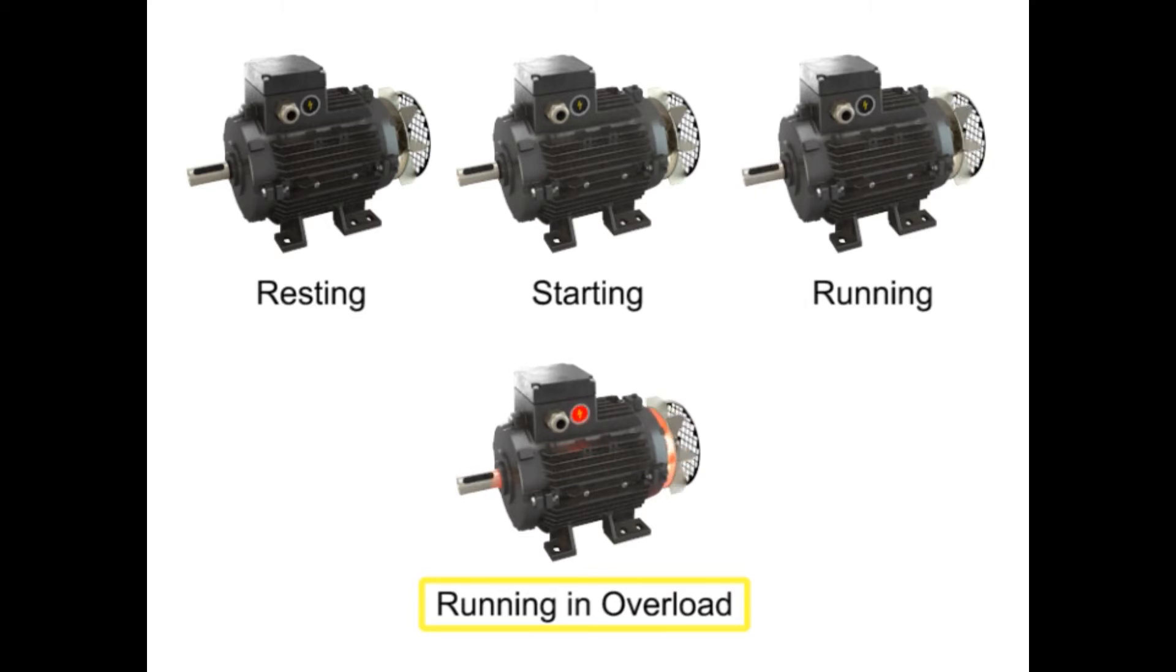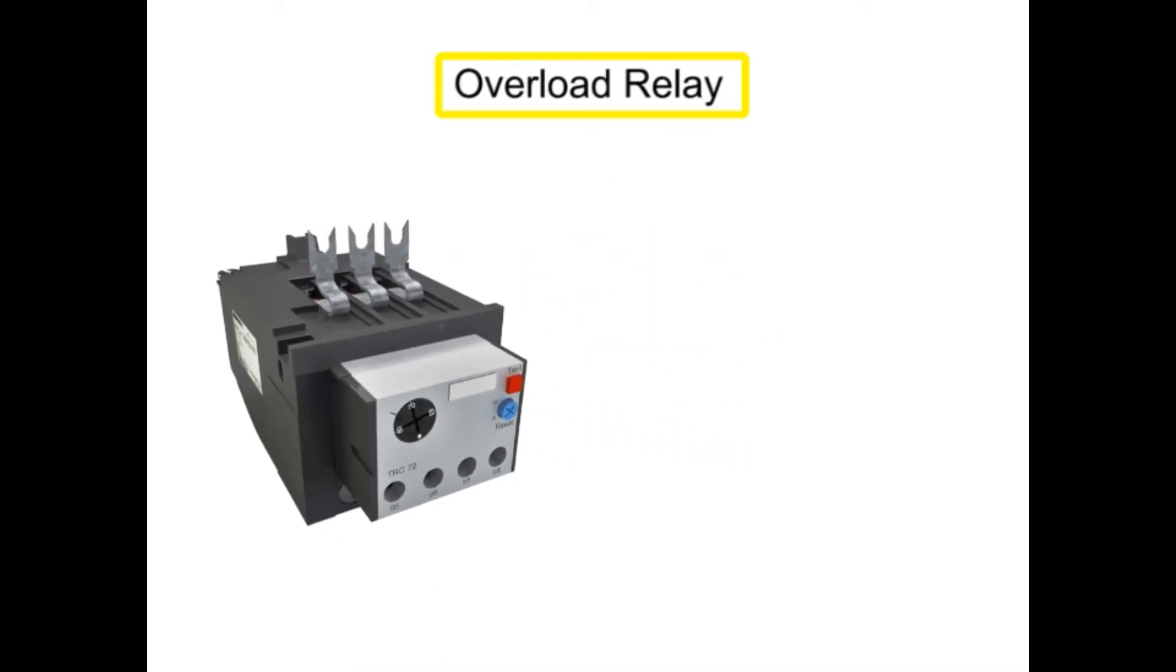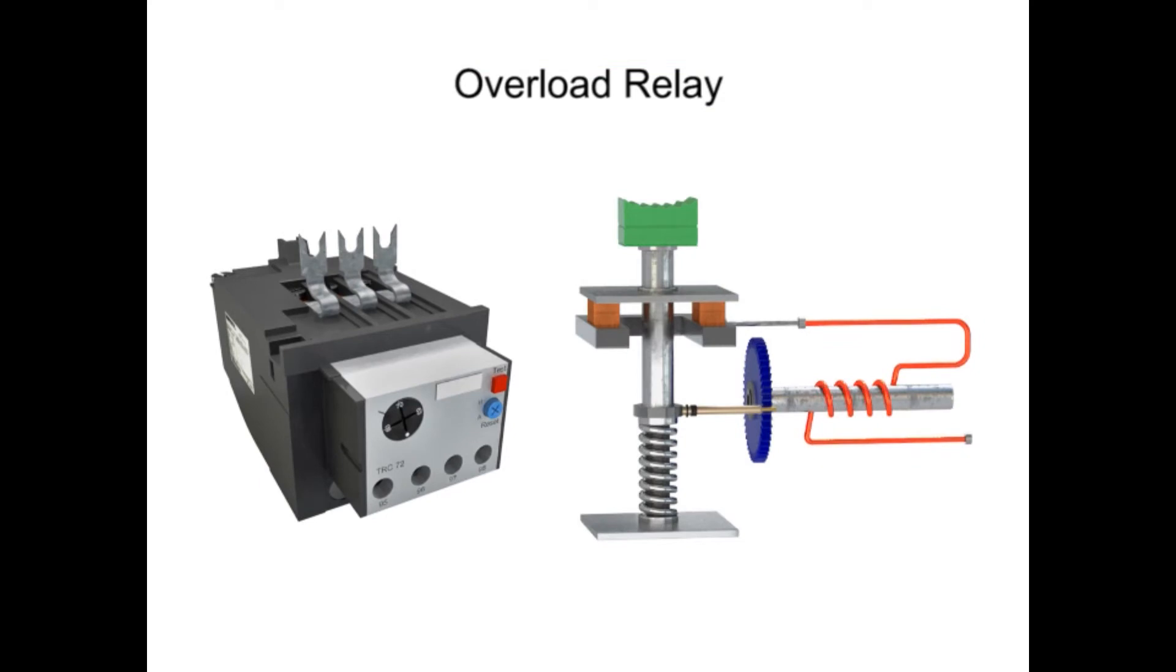To protect motors from running in overload, manufacturers typically protect their products with an overload relay connected to the motor starter. When an overload relay trips, it opens contacts within the control circuit, stopping the motor.